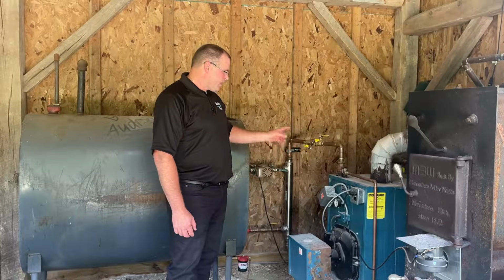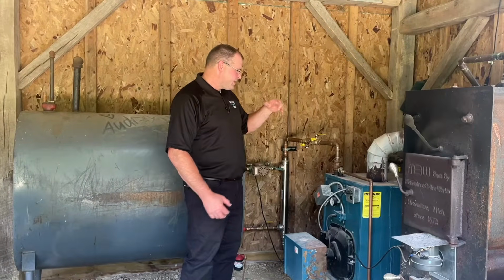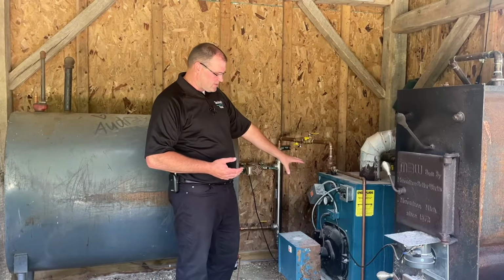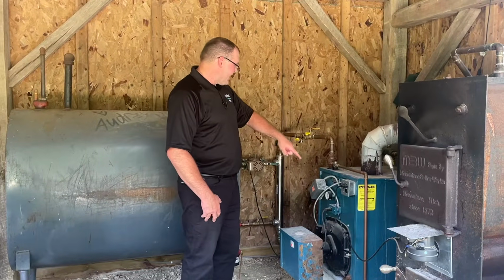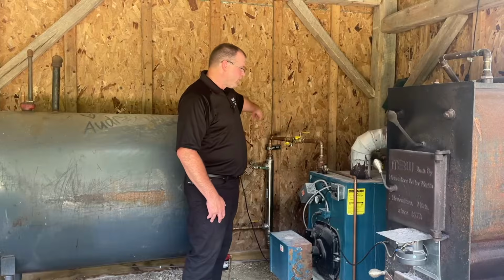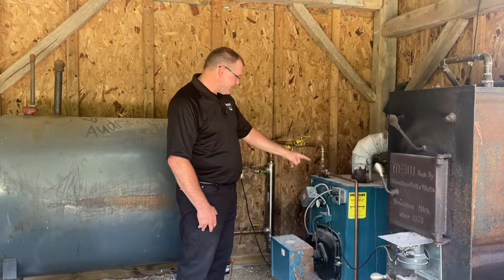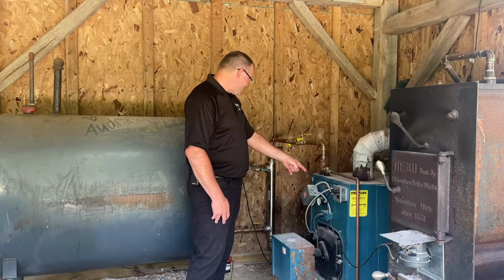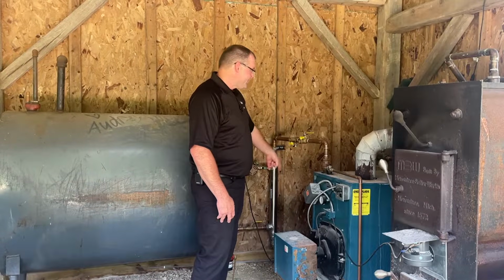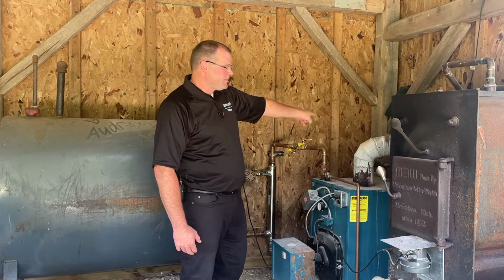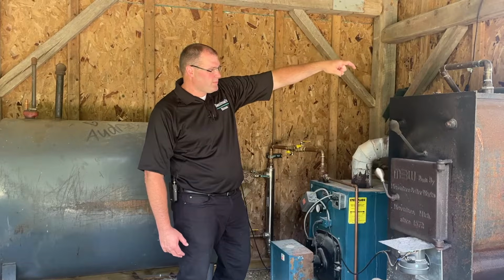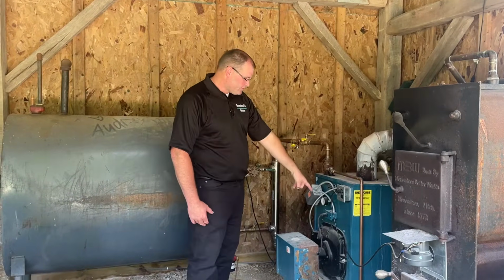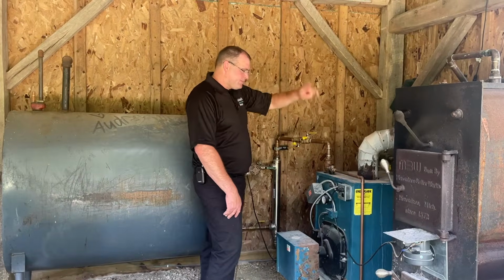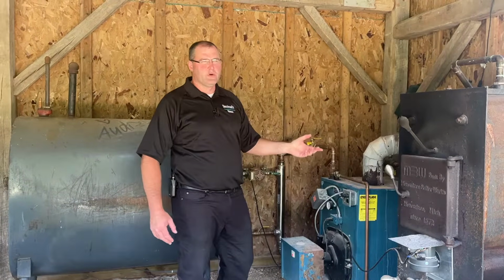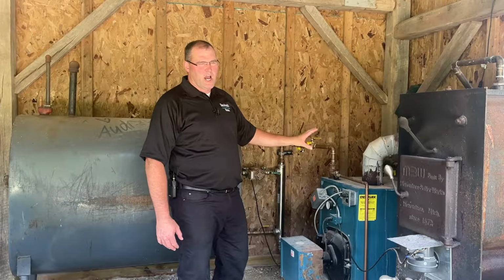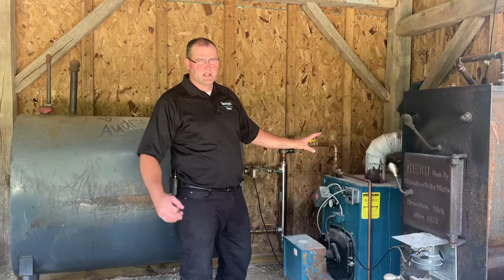So what I did is I ran the water - this probably holds maybe 25 gallons. I ran the water loop, the boiler loop, basically from the boiler here to a pump, then it goes to a pressure tank, an air eliminator, then up into the wood boiler, and out of the wood boiler into the oil boiler, making that boiler loop. I'm calling it a boiler loop because that boiler water never actually touches the pool water.